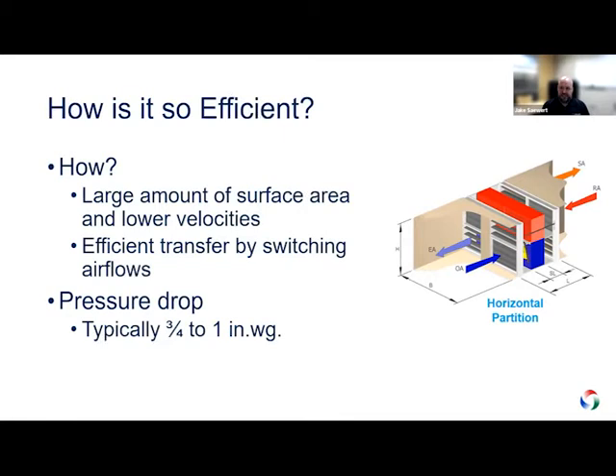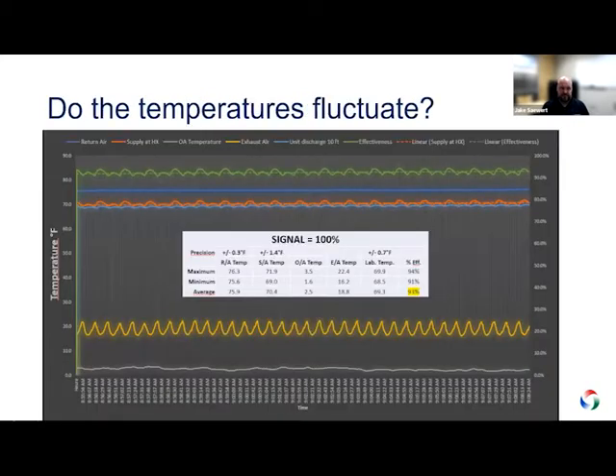Now, a lot of times efficiency comes at the cost of more static pressure drop. You know, typically we're designing these for about 3/4 of an inch to an inch of pressure loss. So it's not too far out of bounds of what you'd expect from an enthalpy wheel or a flat plate heat exchanger for that matter.